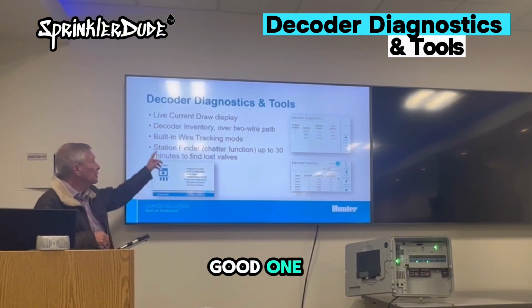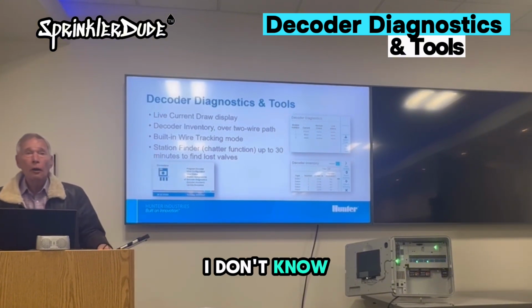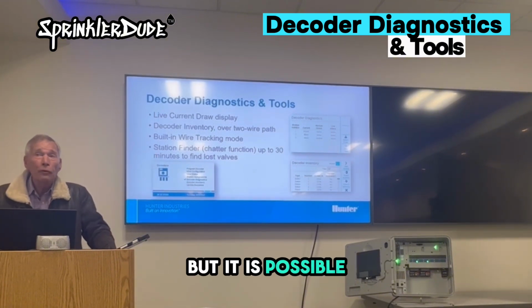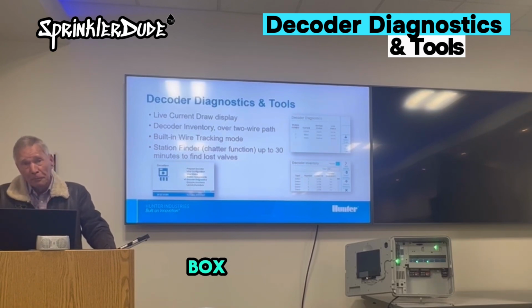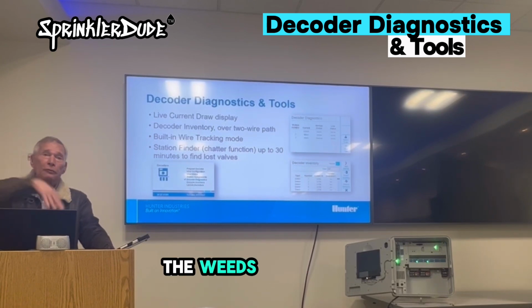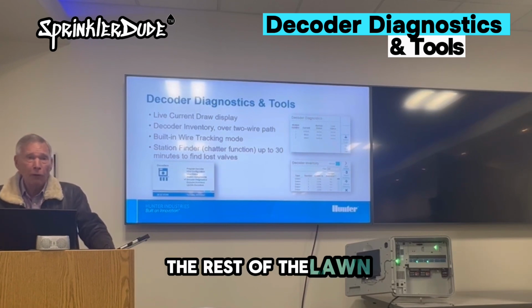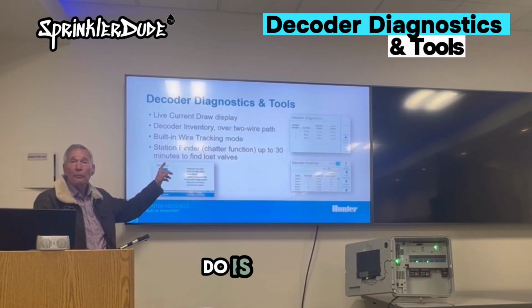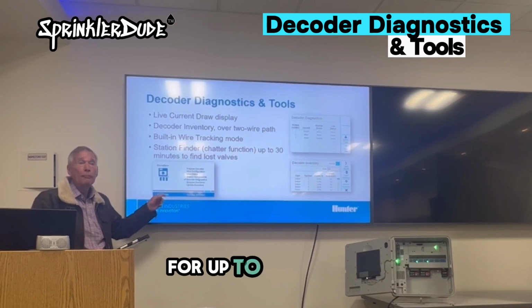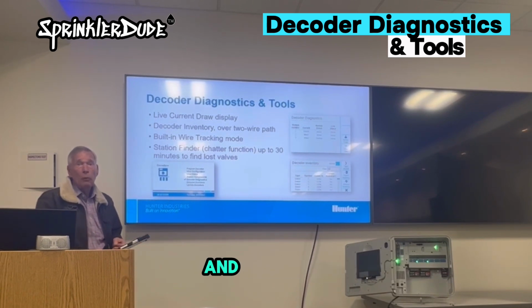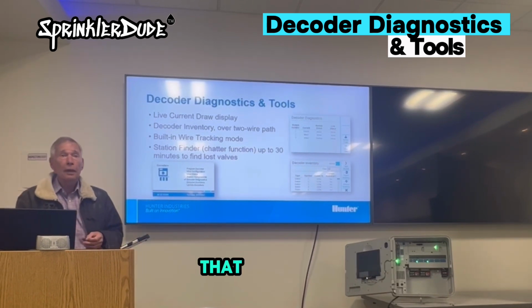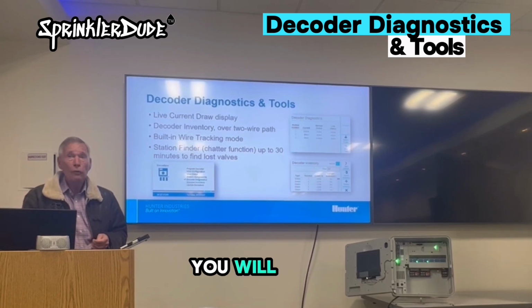And another good one is the station finder. I don't know if this happens in your world, but it is possible to lose a valve box. Mud washes over the top, the weeds grow on it, looks just like the rest of the lawn. What this will do is chatter the solenoid for up to 30 minutes. And what we found in testing, if you chatter that solenoid a lot longer, you will smoke the solenoid.